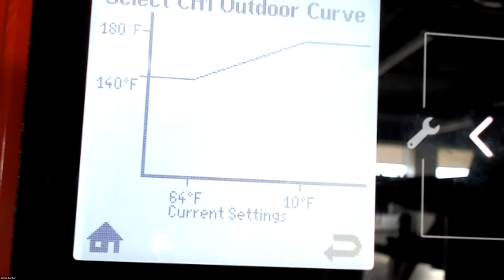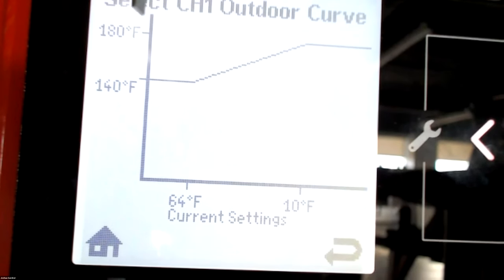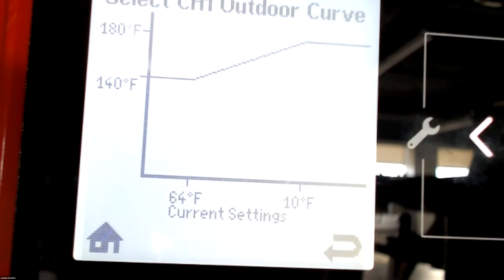65. Okay. And then it gets down to 140. So this outdoor reset, on all of our outdoor resets, whether it's us, Taco, Tekmar, doesn't care about the boiler. Your outdoor curve and your outdoor reset is determined by the radiation in the house. That's what you need to know. And that's what you need to have for information on setting your outdoor curve. This outdoor reset is just to save you a few bucks, or save the homeowner a few bucks, in the shoulder seasons, right? To reduce that temperature because we technically don't need 180 degrees when it's 40 or 50 degrees out, depending on the system.